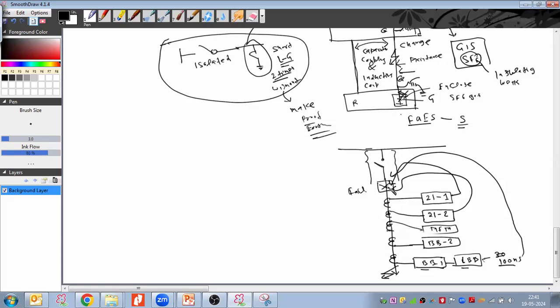Means if any fault happens from the bus bar till here, this fault will come under which protection zone? The bus bar protection zone, right? And when the bus bar protection operates, it operates after the 100 milliseconds delay, which means the fault is happening but your breaker is not operating. There is some delay in there. So this is our point one about the breaker, and point two is about the fault happening in this zone.